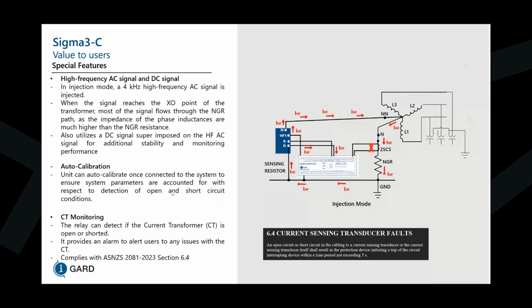This complies with the Australian Standard 2081-2023 Section 6.4, where it indicates that an open circuit or short circuit in the cabling to a current sensing transducer, or the current sensing transducer itself, shall result in the protection device initiating a trip of the circuit interrupting device within a time period not exceeding 5 seconds.